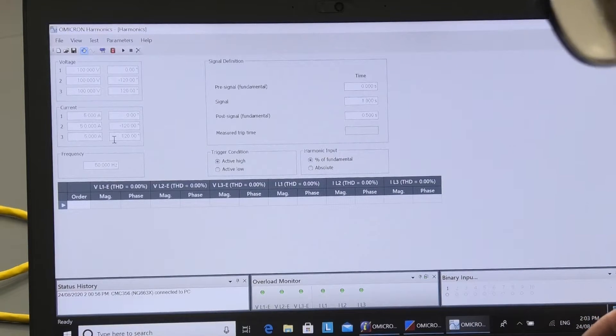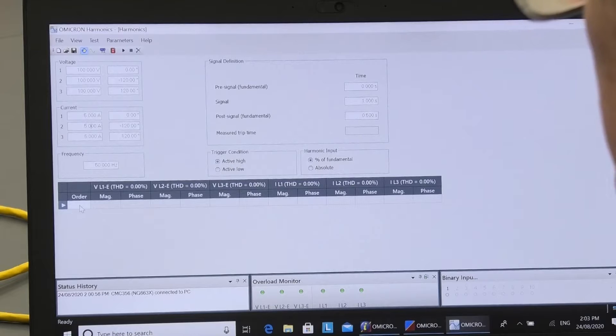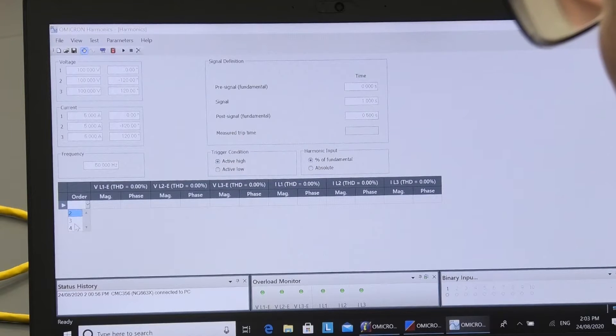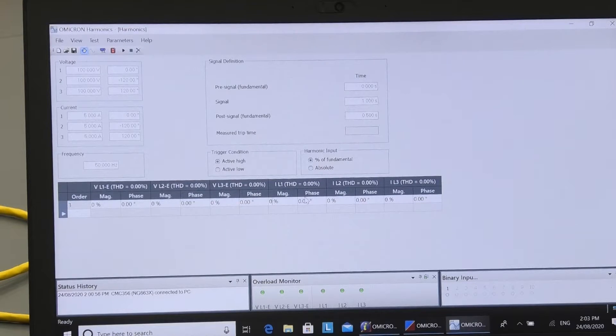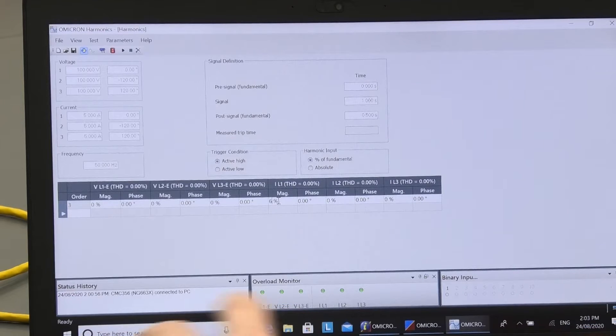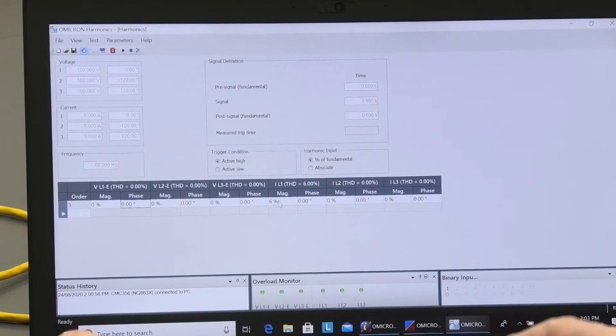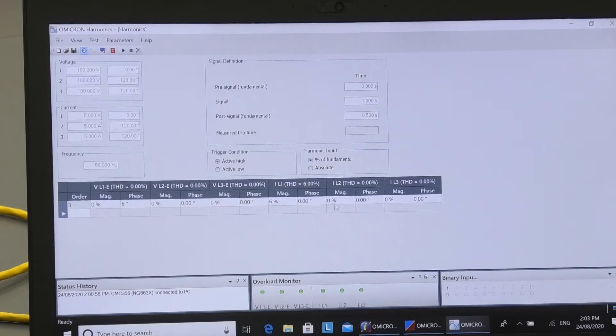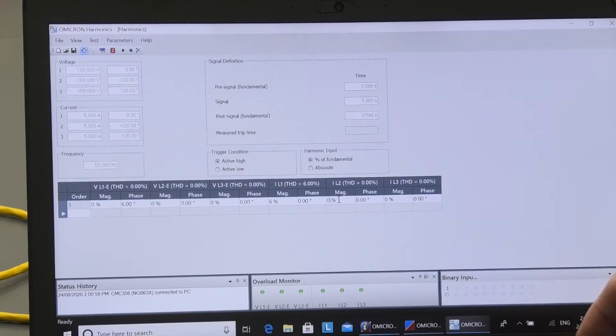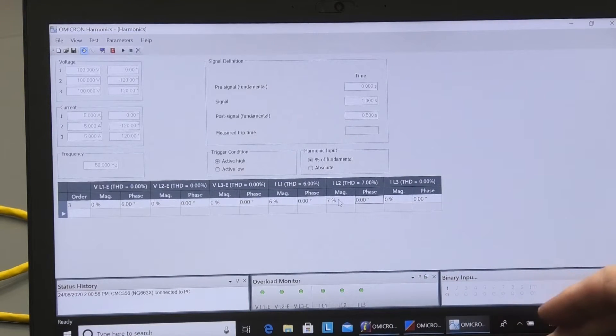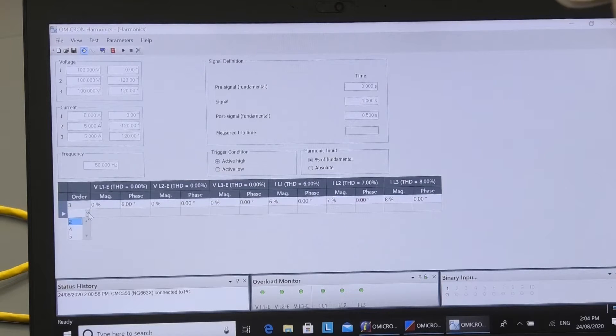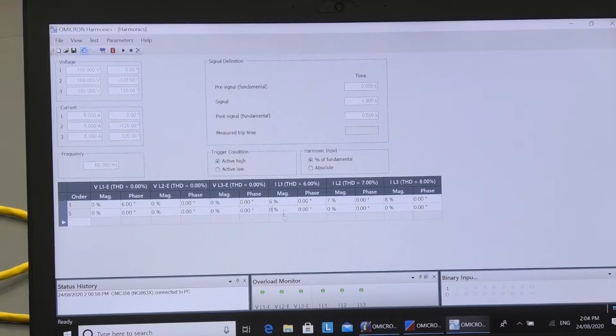And now what I can also add is some harmonic distortion. So on the third harmonic, I'm going to put some. I won't put it on voltage, I'll put it on the current. So we're going to have 6% at 5 degrees, 6% and I'll make this one 7% and make this one 8%.